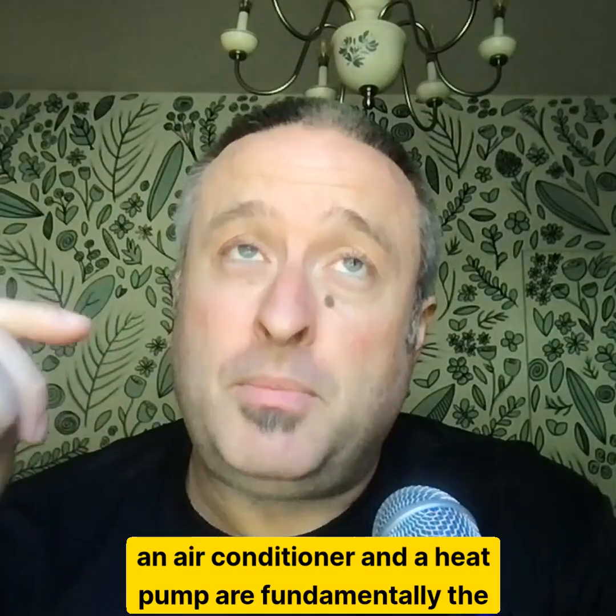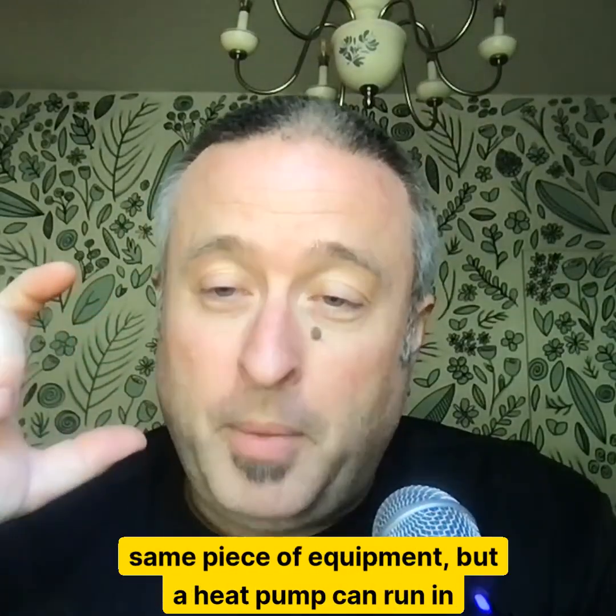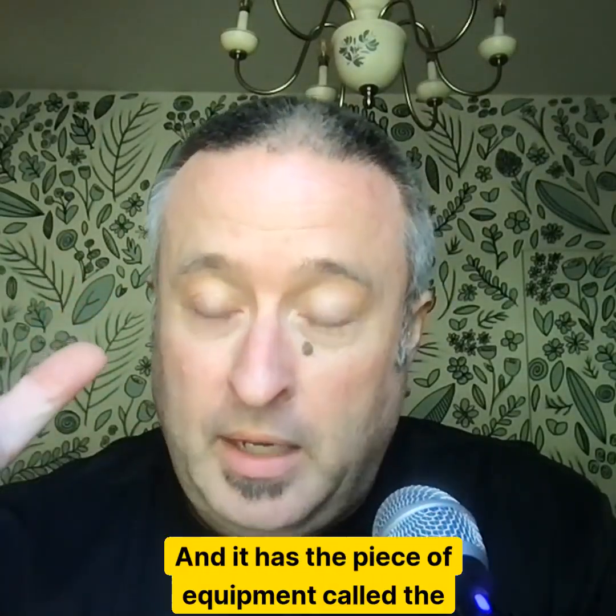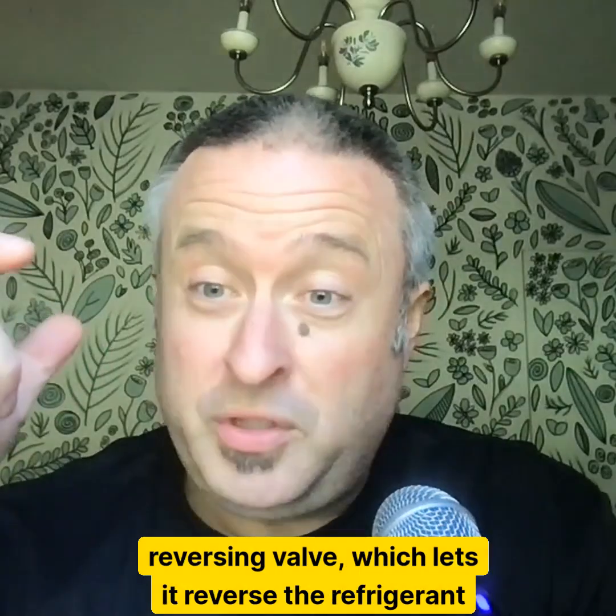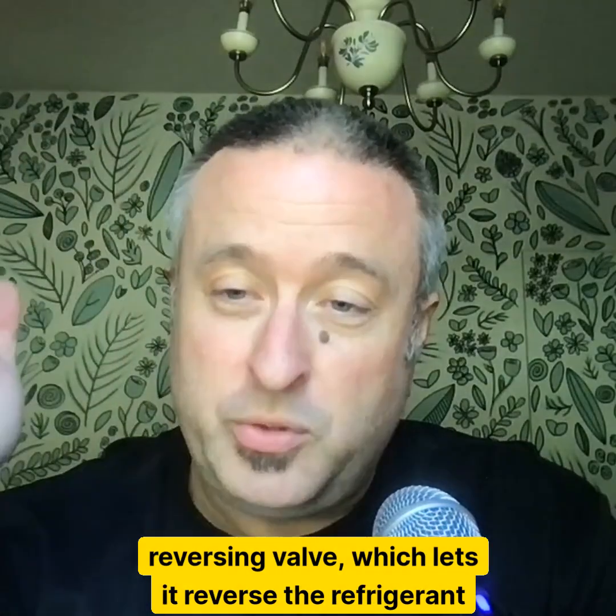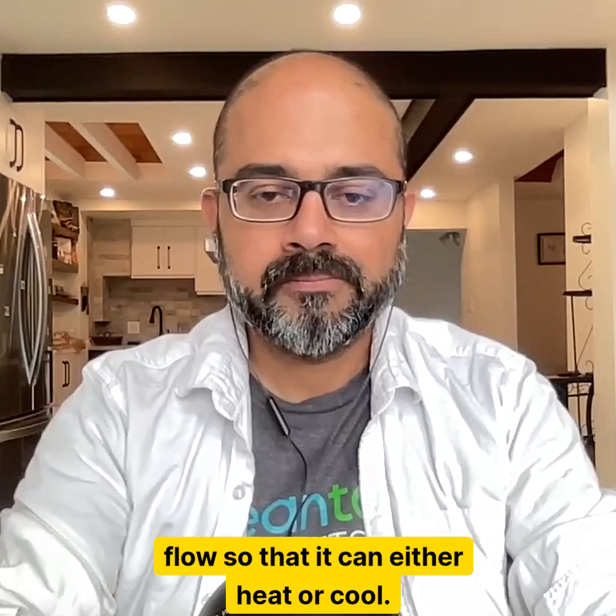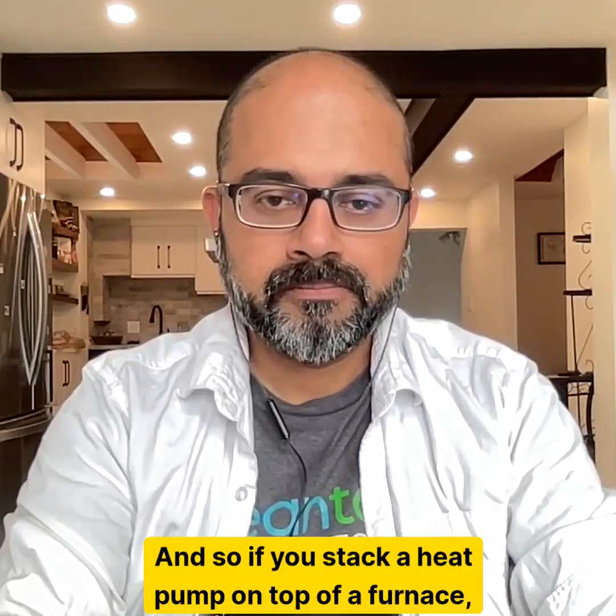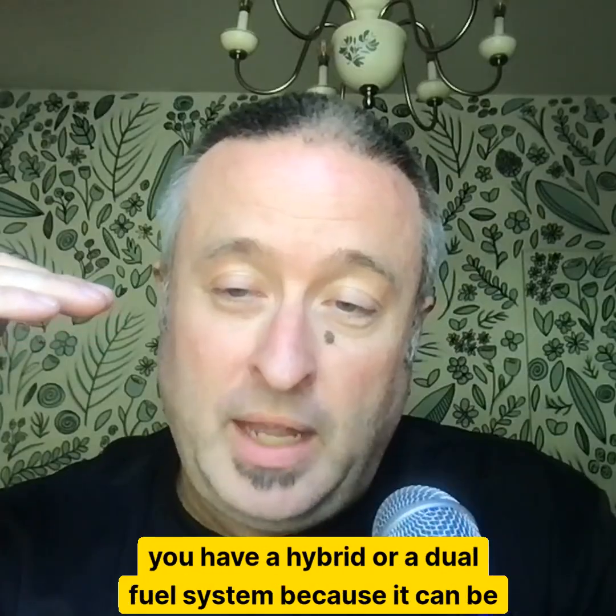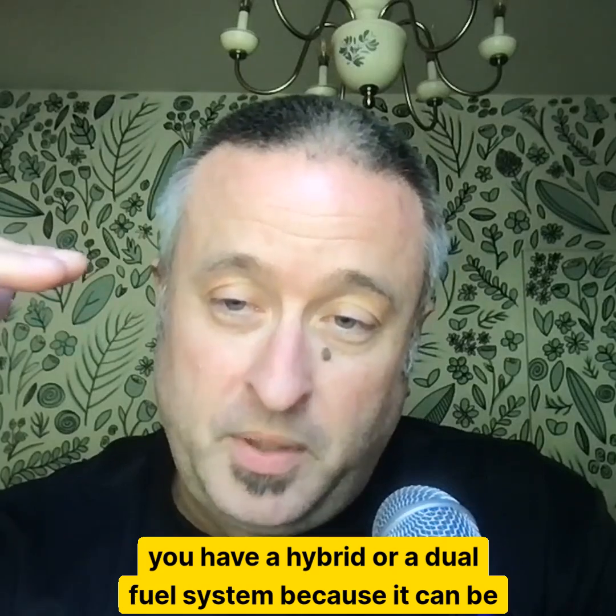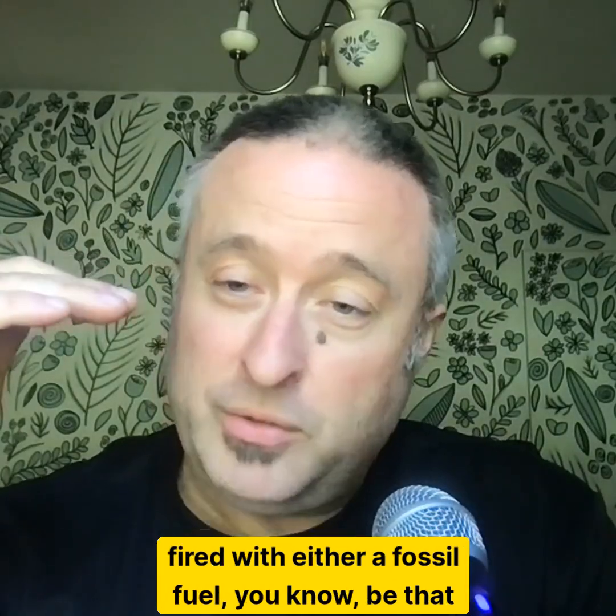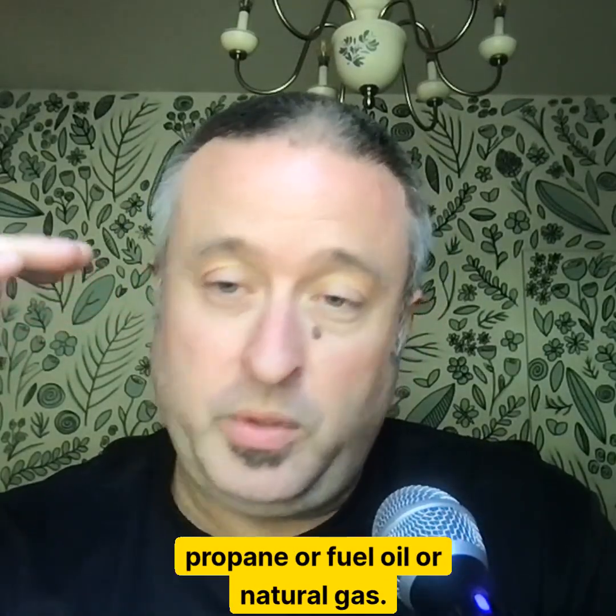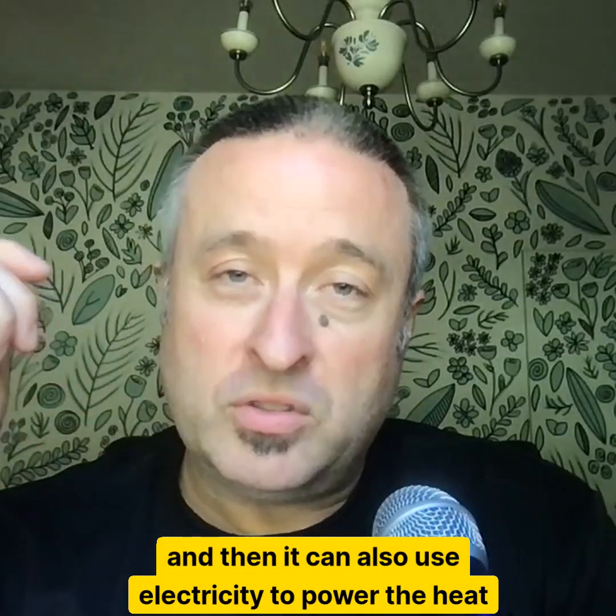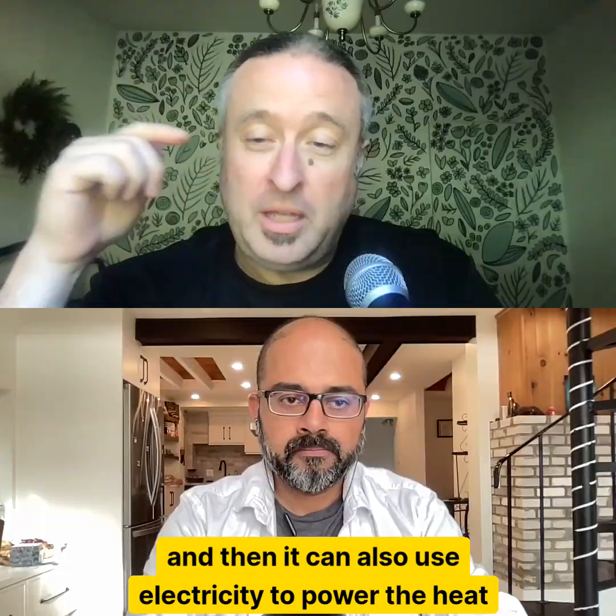An air conditioner and a heat pump are fundamentally the same piece of equipment, but a heat pump can run in reverse. It has a component called the reversing valve, which lets it reverse the refrigerant flow so it can either heat or cool. If you stack a heat pump on top of a furnace, you have a hybrid or dual fuel system, because it can be fired with either a fossil fuel—propane, fuel oil, or natural gas—and it can also use electricity to power the heat pump and heat the house.